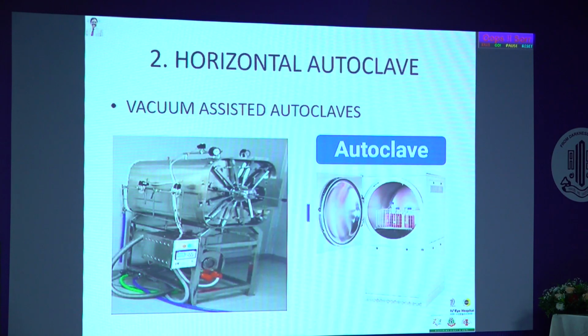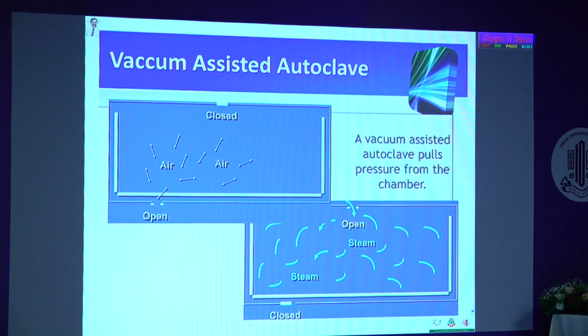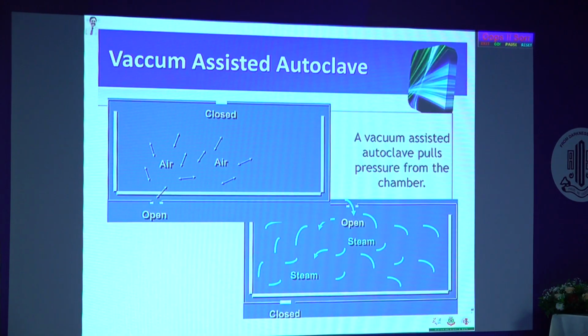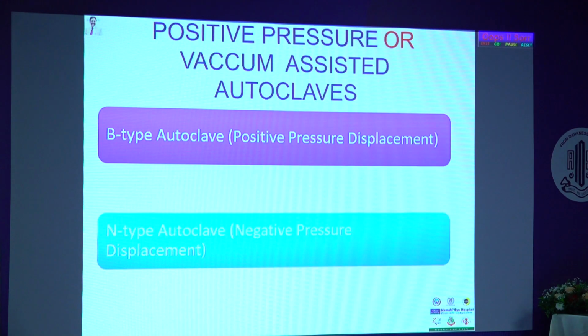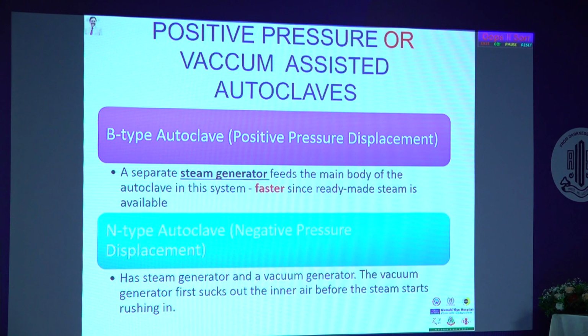So the second type of autoclave commonly used is the vacuum-assisted autoclave. Within a closed chamber, the air is removed first for efficient sterilization, and the pressure buildup happens after with the steam. There are two types of autoclave in this, the B type or the positive pressure displacement autoclave. Here the machine has two parts. One is the steam generator, which gets heated up and produces steam, so there is ready-made steam for the chamber to get heated.